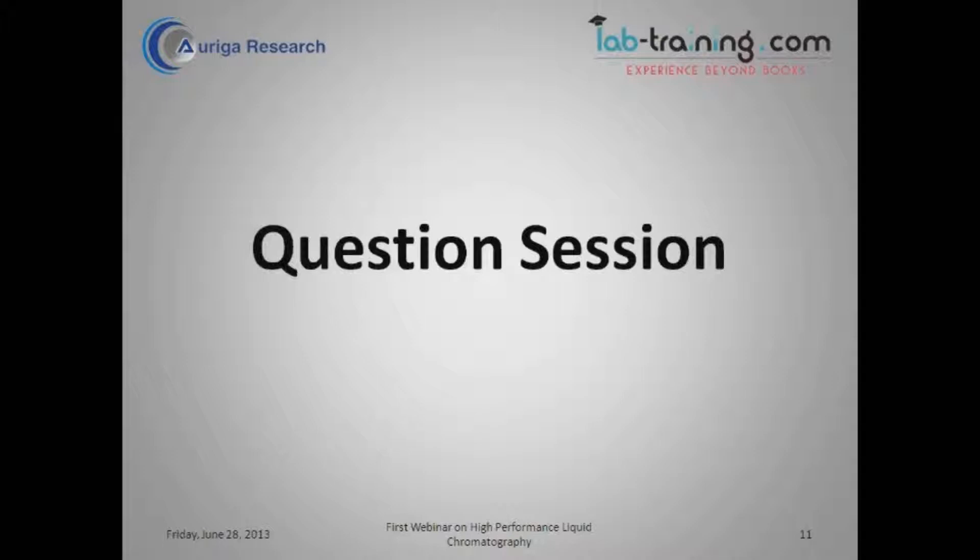Yes. So one has to be very careful when you get a proposal for HPLC because HPLC, as I mentioned earlier, is not a tailor-made plug-and-play system. It has to be configured. So you should get the configuration from the supplier as per your application requirements. Sometimes I do not blame any particular suppliers but they have a tendency to match the configuration as per your available budget. So either they will overquote or they will underquote. So you have to be very clear on your individual requirements and then only you can be sure what you have been quoted is meeting your application needs.